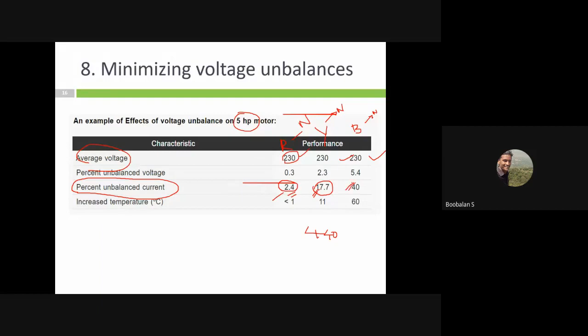So this will lead to a problem - whenever current flow increases in any conductor, it leads to high temperature. If you watch carefully you'll notice it. So something is happening in my 5 HP motor - this much temperature will introduce much heat on my B phase, and B phase will start getting failure. If one phase fails, the motor gets totally failed and we need to go for rewinding.